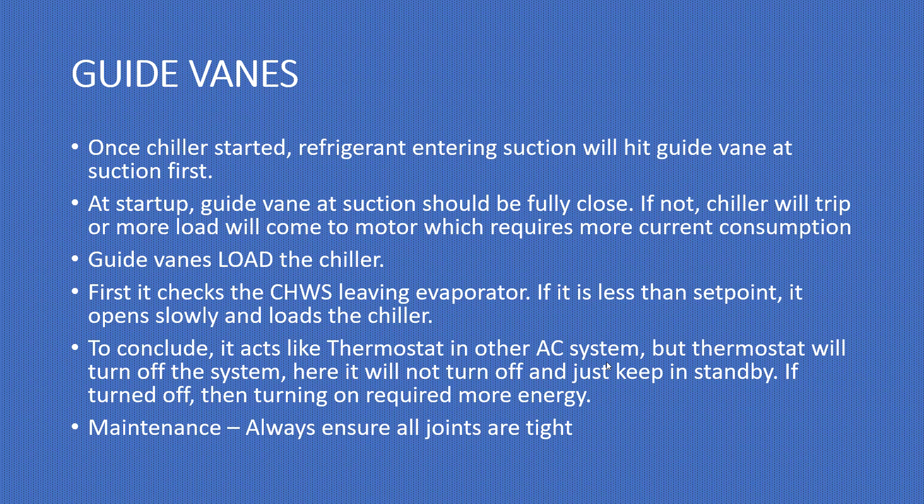Once the chiller starts, refrigerant entering the suction will hit the guide vanes first. At startup, the guide vane at suction should be fully closed — if not, the chiller will trip or more load will come to the motor, requiring more current. Gate vents load the chiller gradually: it first checks the chilled water leaving the evaporator, and if it is less than the set point, it opens slowly. It acts like a thermostat in other AC systems, but here it will not turn off the system — it keeps it in standby, because turning off and turning on again requires more energy.